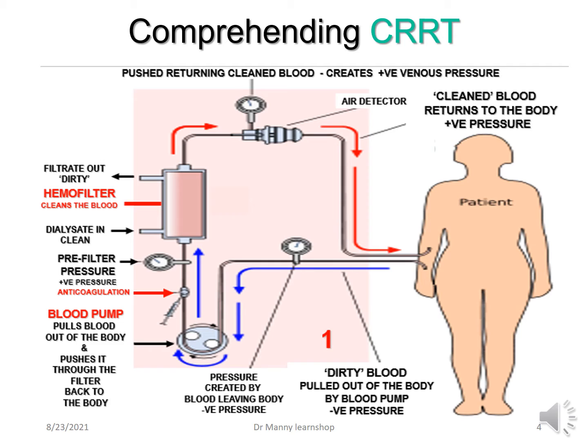The blood pump is what's responsible for pulling the blood out of the body and then pushing it through the filter back towards the body. The hemofilter is what cleans the blood. But before the blood gets to the filter, typically there may be anticoagulation that's provided, if it's been ordered, to prevent filter clotting. The pre-filter pressure is typically positive because the blood pump is pushing blood towards the filter. It's got to go through a very fine semi-permeable membrane, which is the filter. And in the process, it's the hemofilter that cleans the blood of whatever you want to get rid of. Either getting rid of water, getting rid of urea, getting rid of creatinine, getting rid of both.